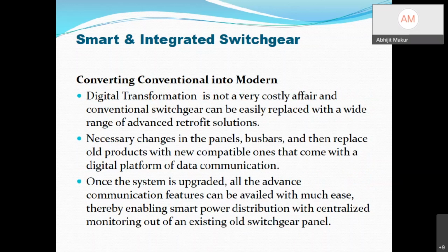Converting conventional to modern. It is not possible for utilities or any customer to entirely replace all existing switchgear with smart switchgear in one go. But digital transformation is now not a very costly affair, because we only need to replace some modules with a wide range of advanced retrofit solutions. Necessary changes in panels and bus bars can take place, and old products and new compatible ones come with the digital platform of data communication. Once the system is updated, all advanced communication features can be availed with the same ease, thereby enabling smart power distribution with centralized monitoring out of the old switchgear panel. Next.